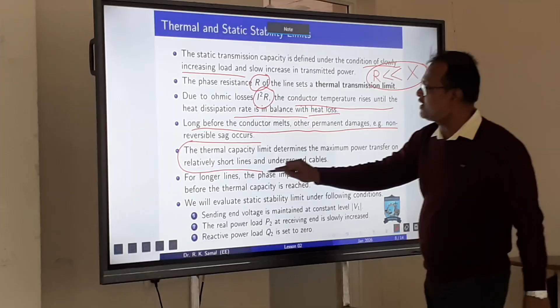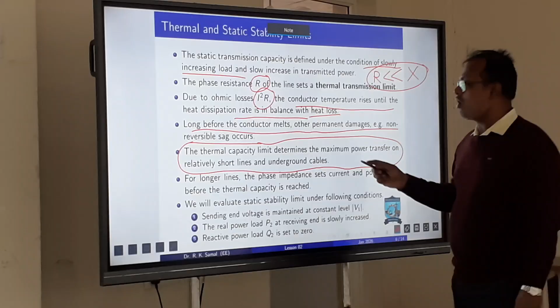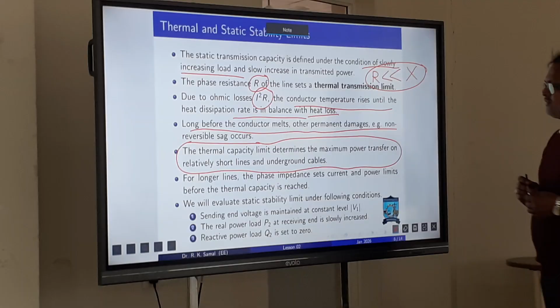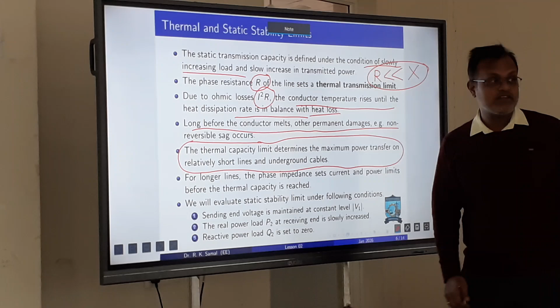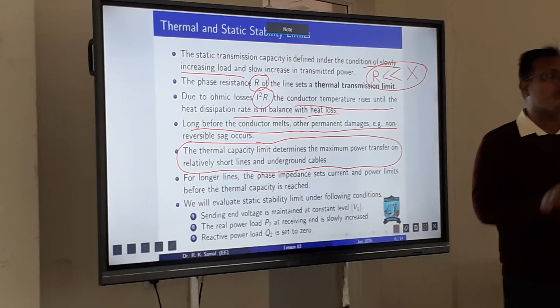The thermal stability limit, thermal capacity limit, determines the maximum power transfer on relatively short lines and underground cables. Okay, maximum power transfer. Short lines and underground cables we consider thermal limit. Okay. For longer lines, the phase impedance sets the current and power limit before the thermal capacity is reached. That means the stability limit is reached before the thermal limit. Okay, for longer lines, we are not bothered about the thermal limit.